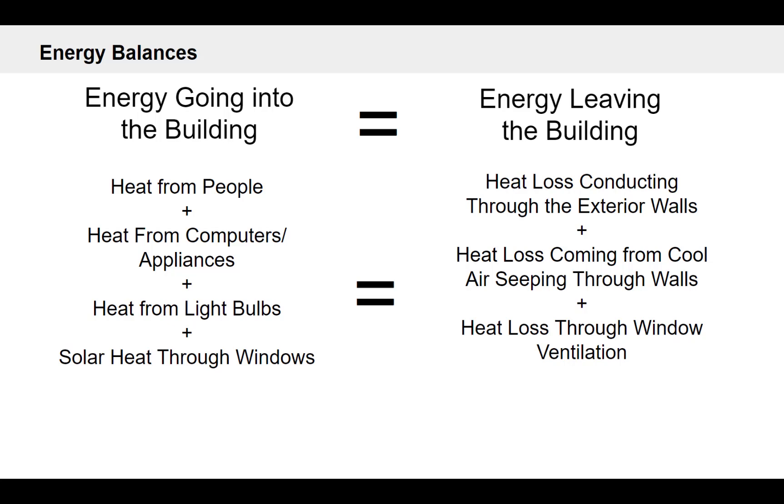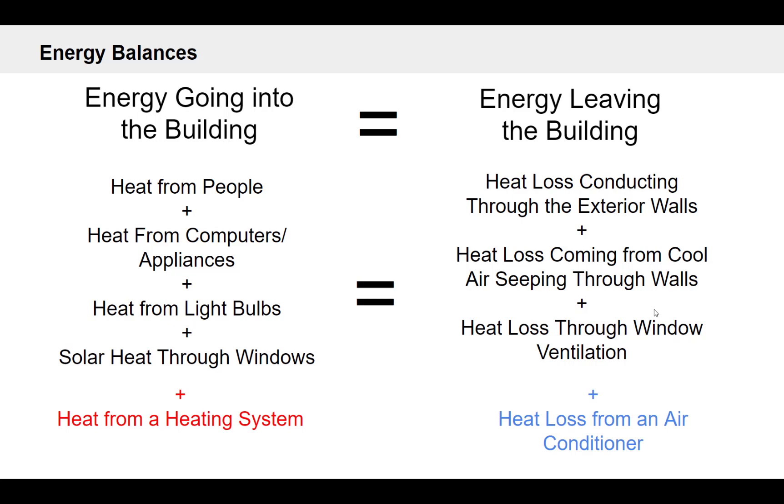So let's just replace the system of myself or generally the word system with building. And you essentially have what's going on under the hood of every single energy calculation engine that exists right now. So essentially, the calculation that's being performed is that all the energy that goes into our building, let's say it goes into our single family home, eventually has to leave the building one way or another. So the energy that goes into a building, some of the things that may put our energy into our buildings would be things like heat from people or heating from computers or from appliances or from light bulbs or the solar heat gain through windows. All of these are going to add heat to the inside of our building. At the same time, heat is going to be leaving our building under typical conditions. If it's colder outside than inside, then heat is going to be conducting through the walls and the roof to the outside. You're going to get some heat loss from cooler air potentially seeping through the walls or even heat loss through ventilation, purposefully done ventilation that you're bringing into the building.